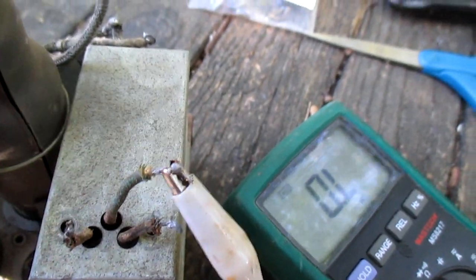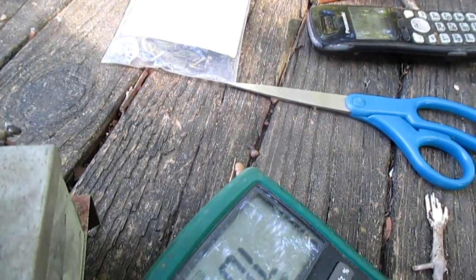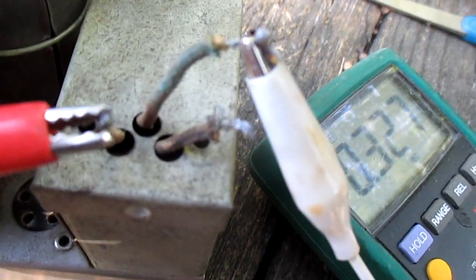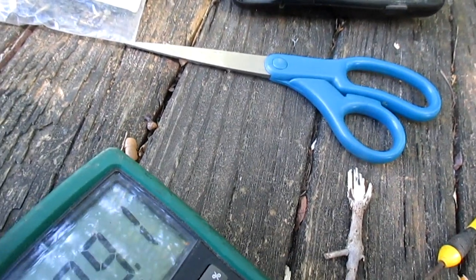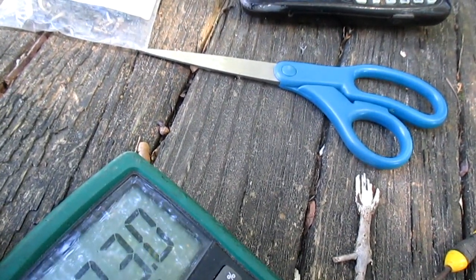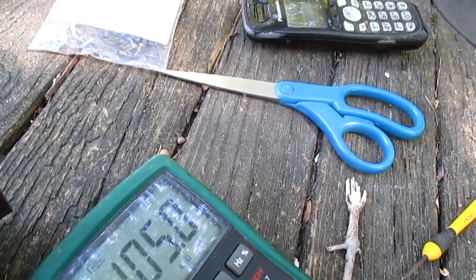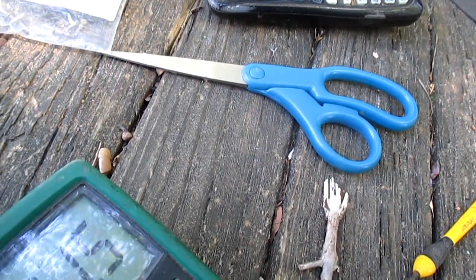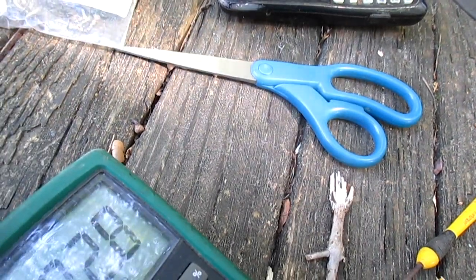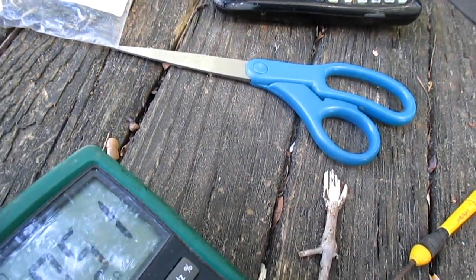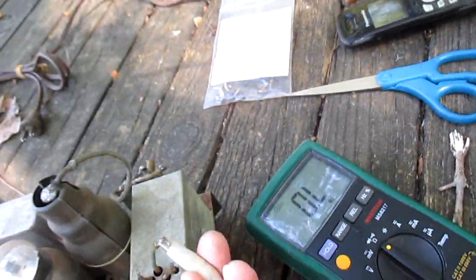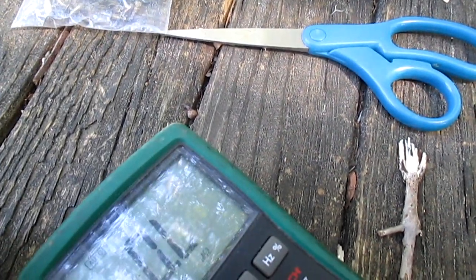This is the ground, which I believe the transformer has a center tap connected to ground. Let's see if this is any good, once the meter decides what it wants to settle on. Well, we're going to say 105 ohms, and about the same for that side. So that is good, just reading directly across the winding.